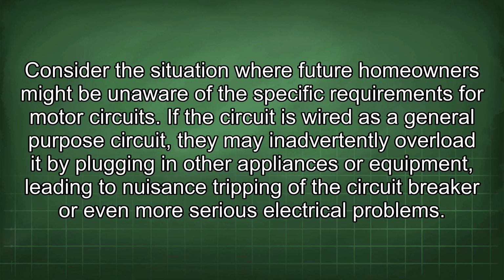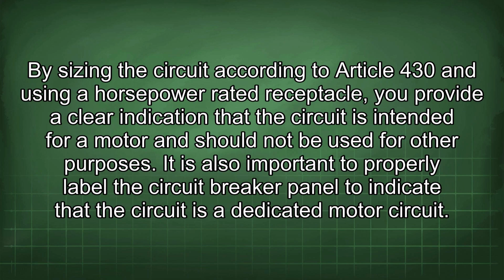Consider the situation where future homeowners might be unaware of the specific requirements for motor circuits. If the circuit is wired as a general-purpose circuit, they may inadvertently overload it by plugging in other appliances or equipment, leading to nuisance tripping of the circuit breaker or even more serious electrical problems. By sizing the circuit according to Article 430 and using a horsepower-rated receptacle, you provide a clear indication that the circuit is intended for a motor and should not be used for other purposes.